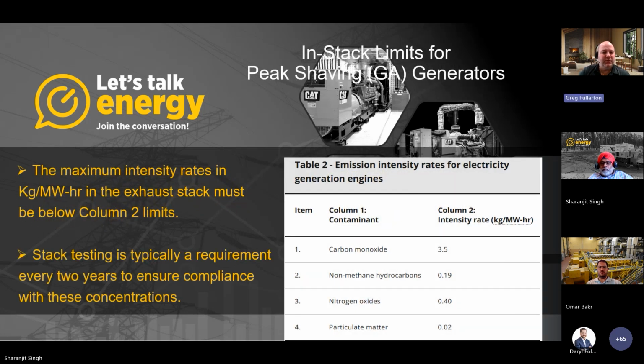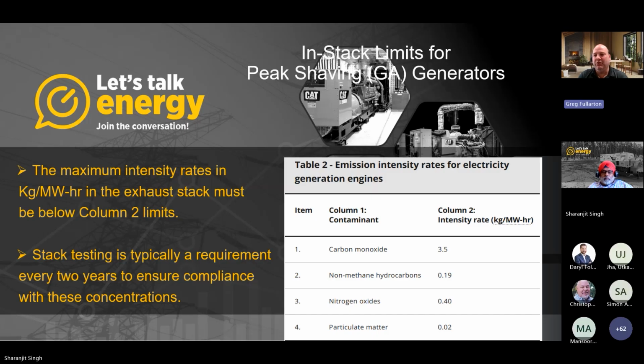So this is what I'm talking about. This is not a standby generator. This is to basically island the facility. The maximum intensity rates in kilogram per megawatt hour in the exhaust stack must be below the column 2 limits. So you note the column 2 limits here. You look at nitrogen oxides, it's 0.4, in essence, 0.4 grams per kilowatt hour.